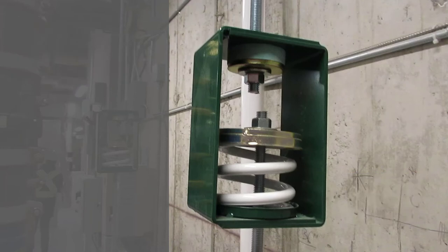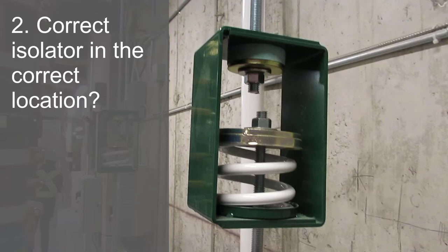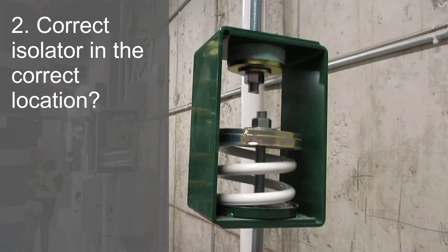Normally we would now check to see if this is the right isolator in the right place, but I wasn't able to find project documentation to support the selections. I did find that this project called for using spring hanger isolators on the first three pipe support points from all vibrating equipment connections and this isolator is on one of the first three points away from the pumps. It's possible these isolators were selected by the contractor without assistance from the vibroacoustics design department, so we'll just be checking for general conformance with good installation practices.